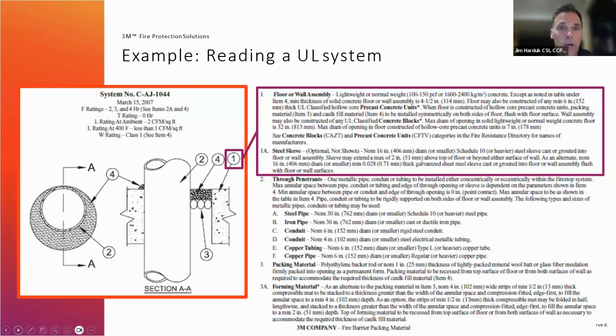So this is an example of what a UL listing or a UL system would look like. So if you go to the UL catalog and you look up the system number, or if you go to the 3M website and you search the 3M system, you're going to pull up the same exact drawing and the same exact information. So every listed system has the same components. At the top of the page, you'll always see the alphanumeric code. So you see the system drawing number C-AJ-1044. Below that is the date which the test was run at UL. And then below that, it'll identify if this can be used for 1, 2, 3, or 4 hours. For this particular system that we're looking at, it lists an F rating of 2, 3, and 4 hours. And typically when they do that, there'll be a matrix somewhere in the system itself, and I'll show you that in a moment here.